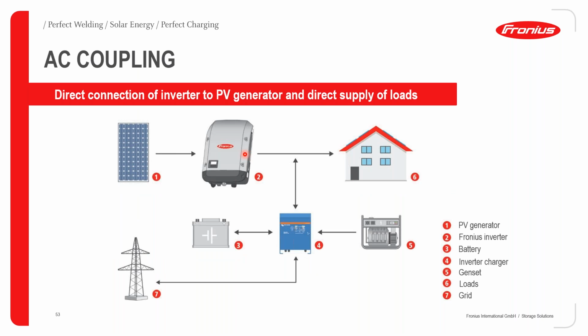When you want to increase the efficiency of this kind of installation, then you talk about an AC coupled installation, whereby we introduce a PV inverter into this kind of setup, and therefore all the energy that is generated by the PV array, the DC power, is fed into the PV inverter. The PV inverter has very high efficiency with the Snap inverter series from Fronius, you can achieve up to 98% efficiency. You are able to convert all that power that is coming from the solar panels during the day, and you're feeding the loads, and the balance or the surplus power is going through the Victron inverter charger, for instance, in this case, to be able to recharge your batteries.